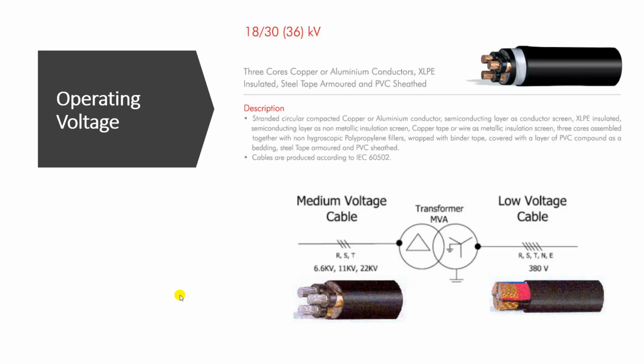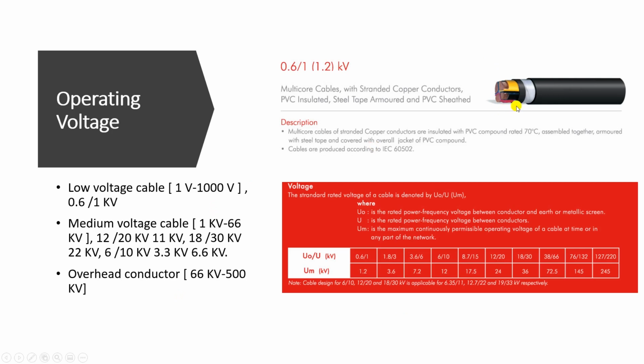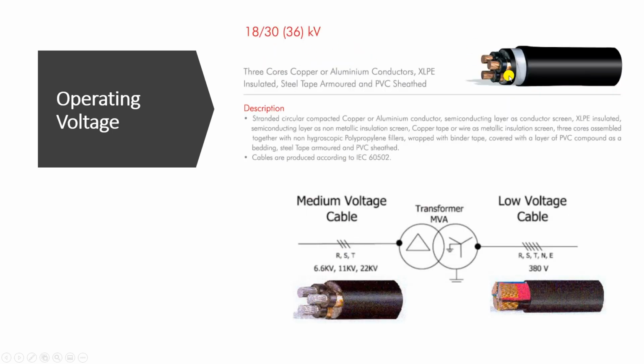Now here is the previous one. This one is a low voltage cable used in a low voltage network, and this one is a medium voltage cable for a medium voltage network. As you can see, 36 kilovolt, or 18/30, is in the range for the medium voltage network, which can be 6.6, 11 kilovolt, 22 kilovolt, and so on. Now as you can see here, here is an example.